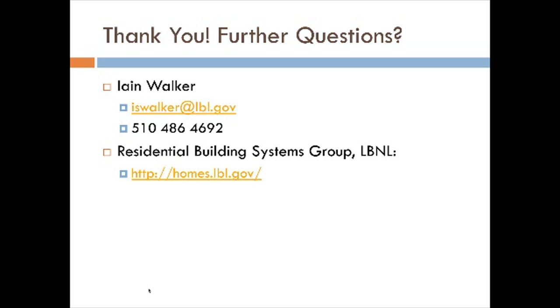I do like the idea, however, of having a control system in a very, very tight house that switches to supply mode only when you turn on the kitchen exhaust. For quite a few reasons. It keeps the home balanced, if you care about that, but also there may be issues in a very tight home. If you don't have a very good blower mounted in the kitchen exhaust, you might not get the airflow that you want, and you might not get the exhaust of the kitchen pollutants you want, in which case balancing that out with a control system that makes the HRV go to supply only would be an assistance to make sure you do get the flow that you want through the kitchen range hood.